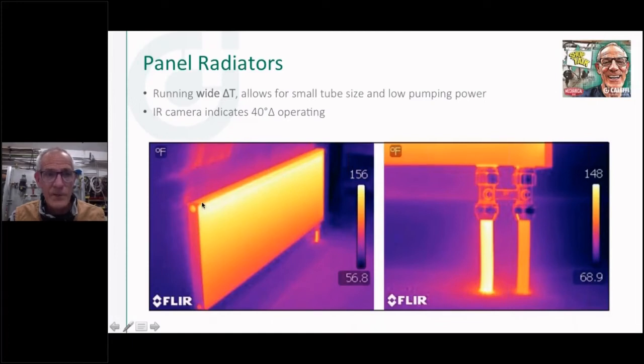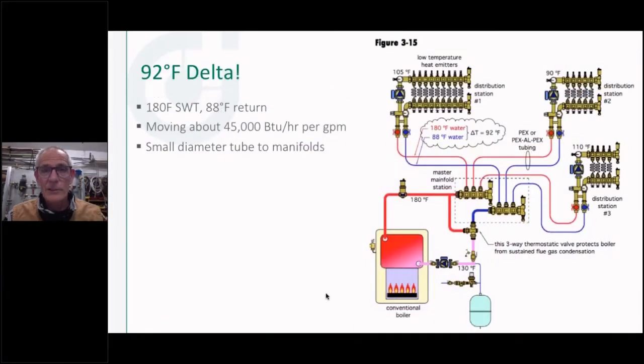I could put a TRV, a thermostatic radiator valve, on that, and I could have room by room or even radiator by radiator adjustability on that system. Nice to have an infrared camera. You can really learn a lot just by looking at things, looking at the color and seeing what's going on, as opposed to always running the numbers and cranking the output on a graph or a chart. The color adds a little interest to it.